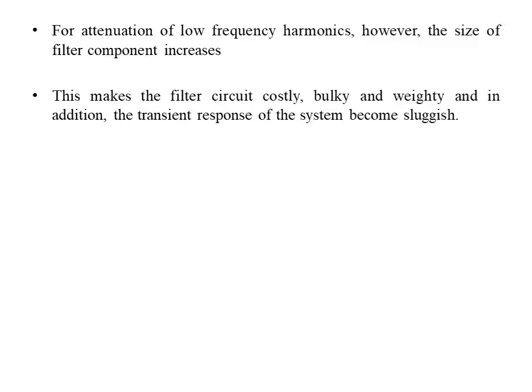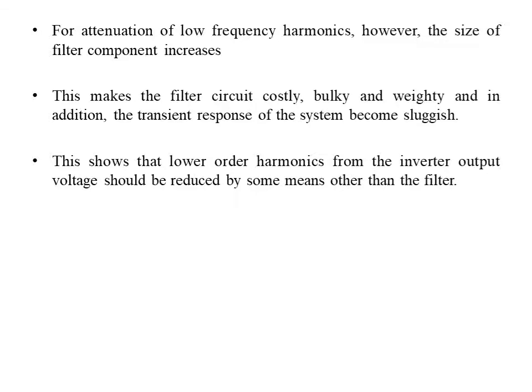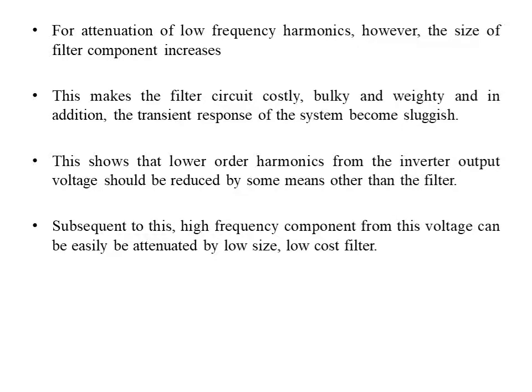This makes the filter circuit costly, bulky, and weighty, and in addition, the transient response of the system will become sluggish. This shows that lower order harmonics from the inverter output voltage should be reduced by some means other than the filter. Subsequent to this, high frequency components from this voltage can be easily attenuated by a low size and low cost filter.